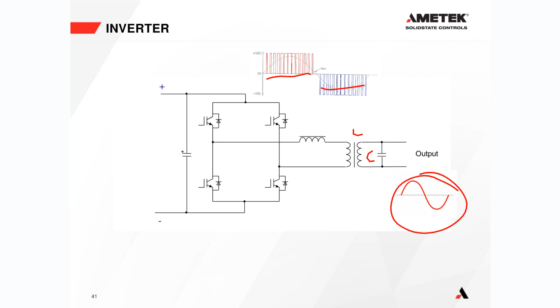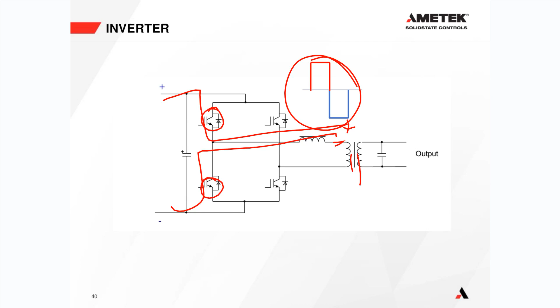Another good question: do your ferroresonant inverters also use PWM? No, they do not. Our ferroresonant inverters generate this, but they don't use an H bridge, it's a slightly different design. We do use IGBTs, but with a center tap primary transformer, we only need one IGBT on the positive side and one on the negative, for small powered systems anyway. We switch the positive or the negative to that side, which changes the direction of this waveform. There's a video in our YouTube library that explains more about how the ferroresonant system works.